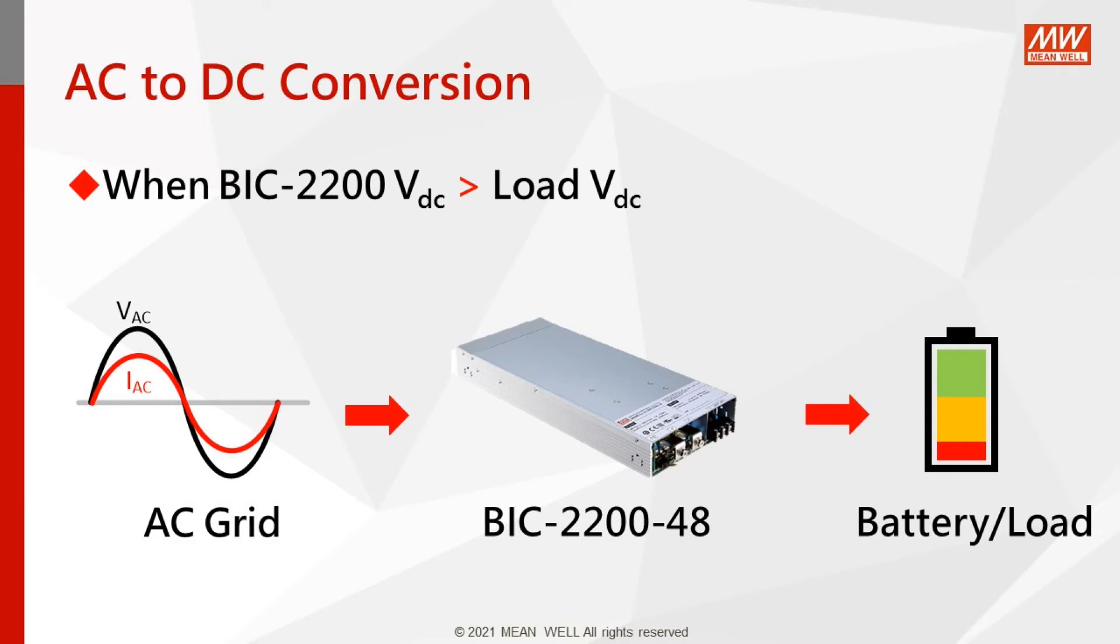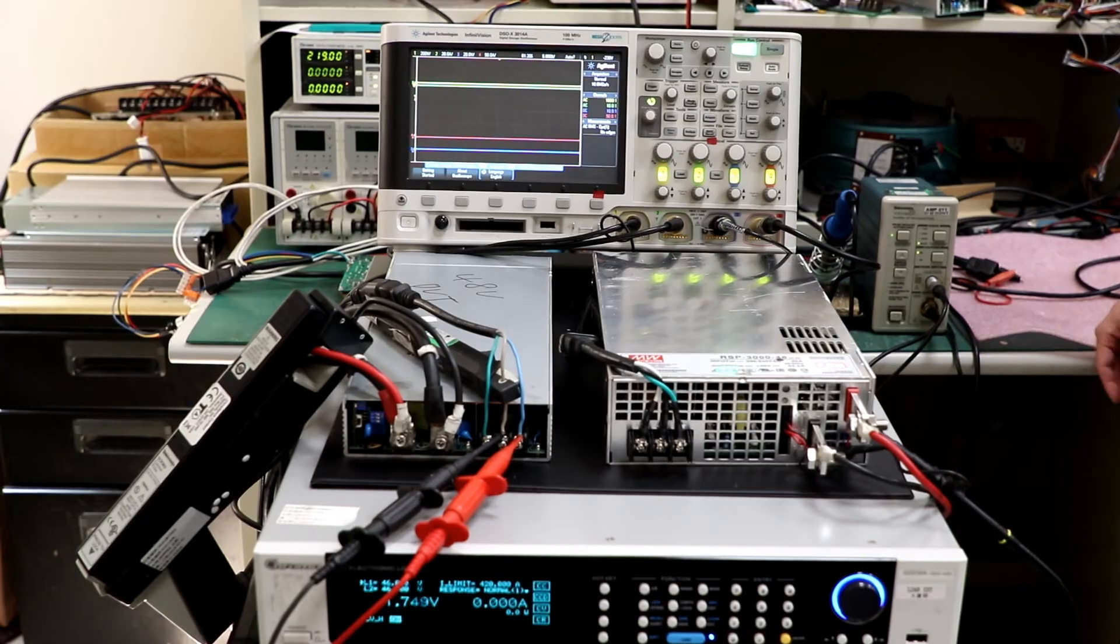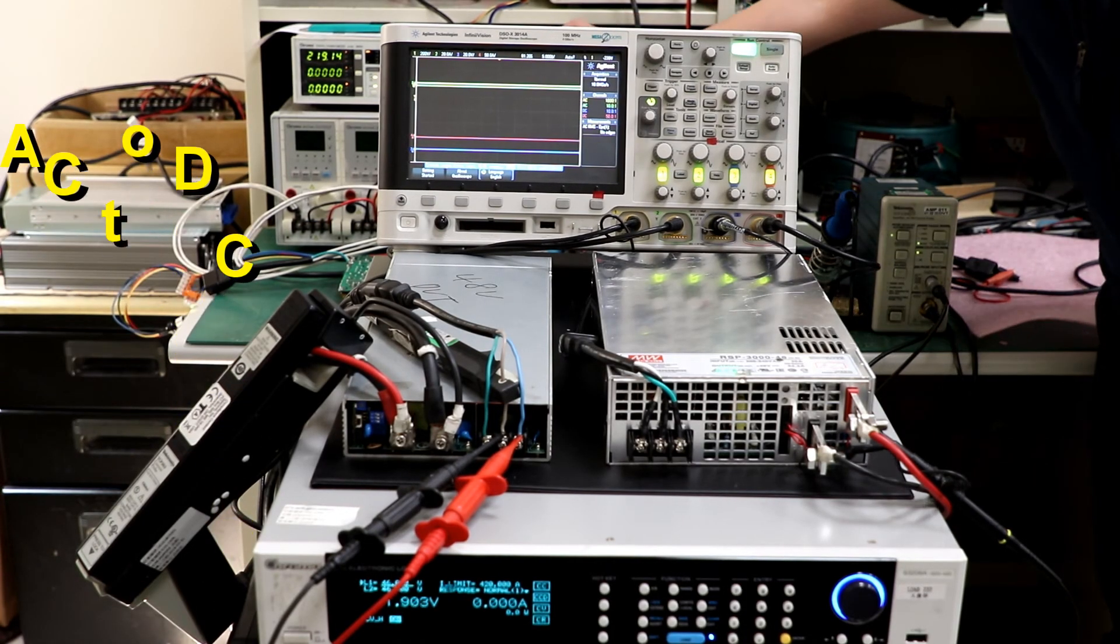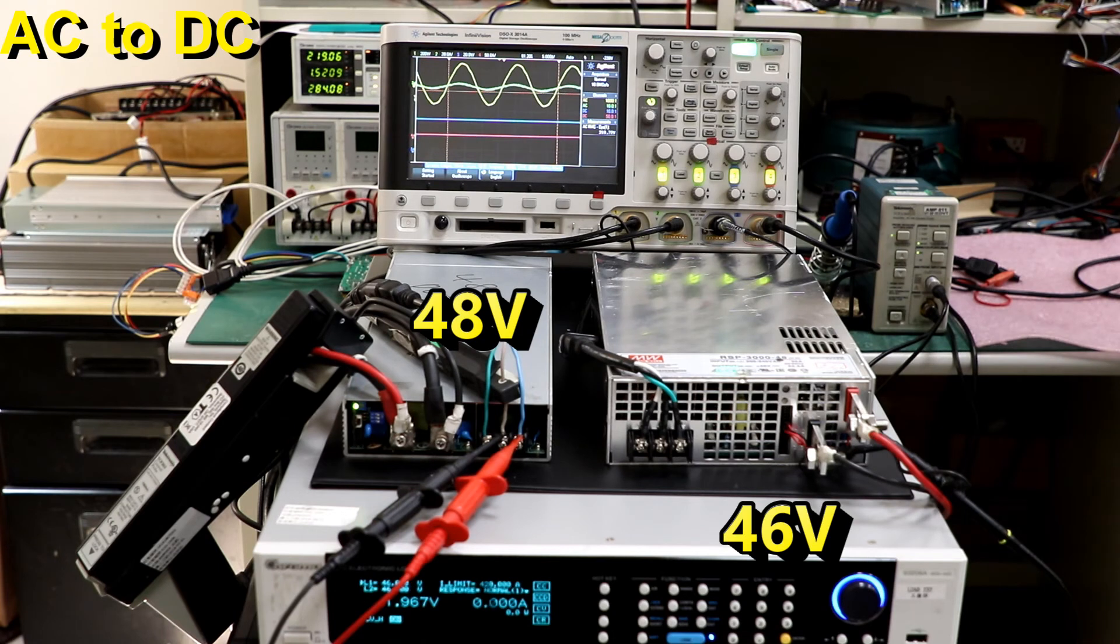Next, we will be doing demonstrations. The first is AC to DC conversion. Connect a DC electronic load to a BIC-2200, 48 volts. Then setting the load at CV mode and 46 volts will force the BIC to do AC to DC conversion.